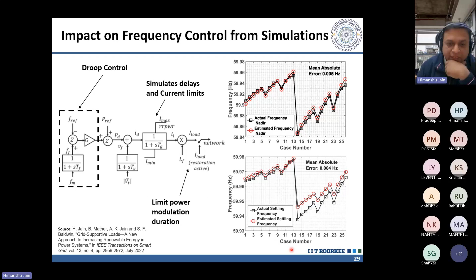Now the question was, if you do implement it, how would you implement that? We have been working on implementing it in appliances as well. Using a similar setup to what I showed you earlier, we dropped our frequency instantaneously from 60 to 58.5 hertz. You can do 50 and then take 5%, it makes no difference to the simulation. 60 or 50 is the same thing for us. Our power demand was roughly 380 something kilowatts, and in about 2 seconds after the drop of frequency, it became around 180 or 190. So the power was halved in about 2 seconds.